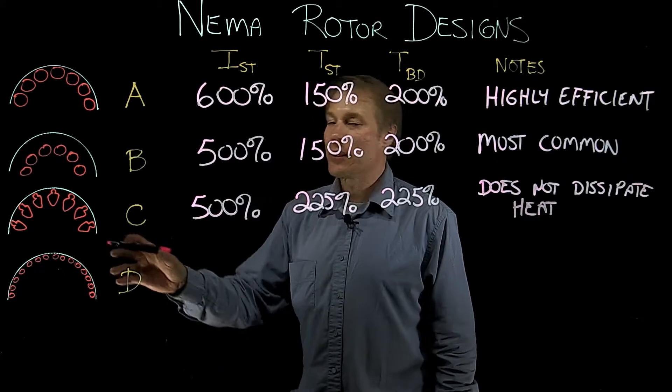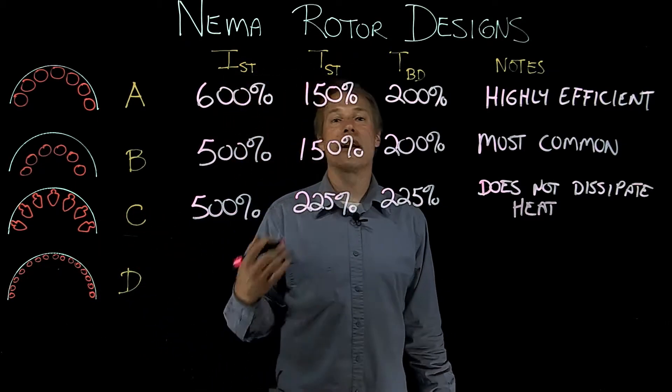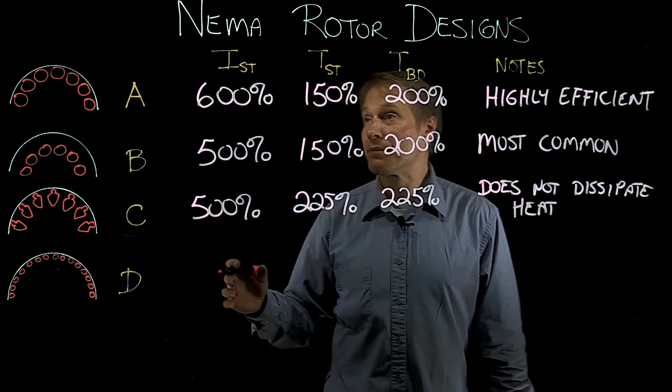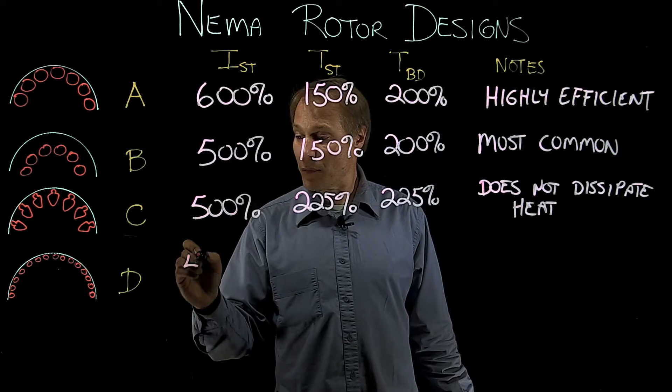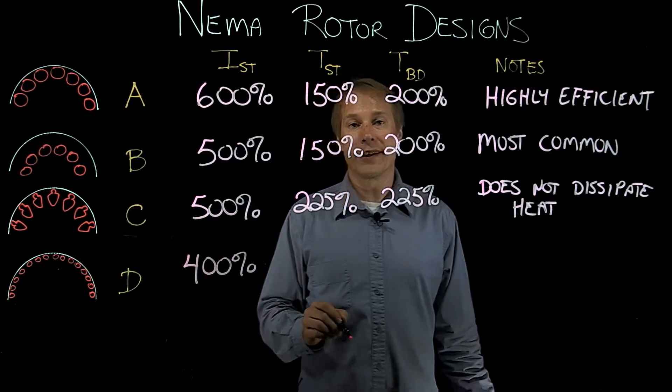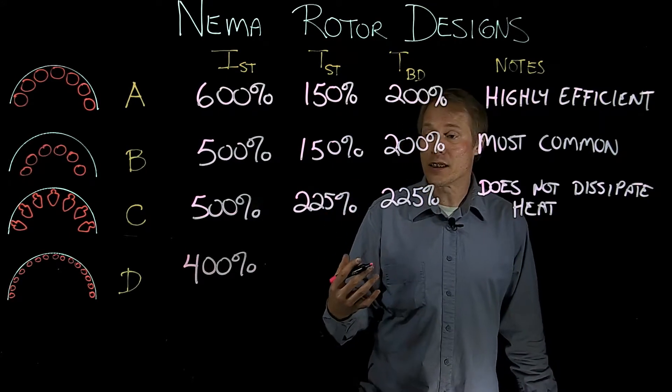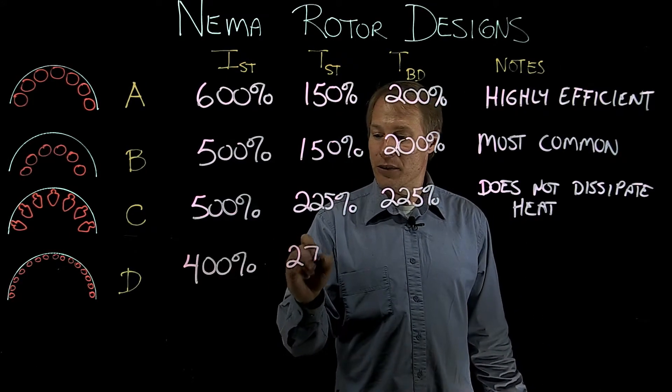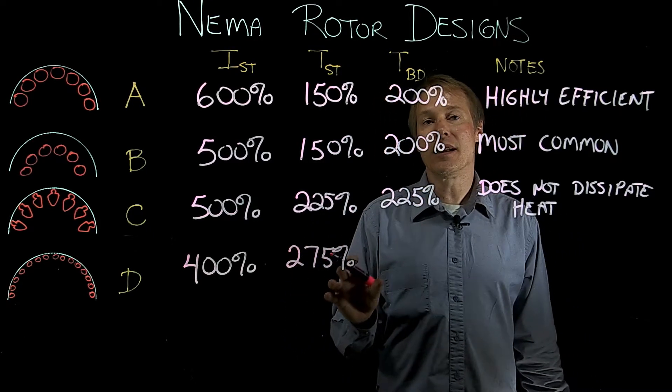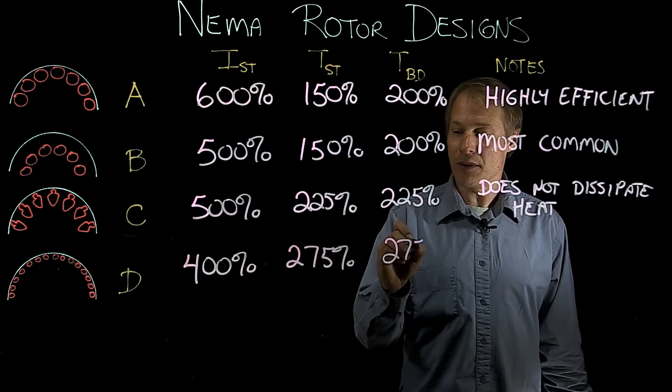And then finally, we've got the NEMA-D design. As you can see, the rotor bars are much smaller, which gives us higher resistance. So that'll make the starting current go down even more. So now we have, let's say, 400% of FLA. But the starting torque will be higher because now it's all resistive. And that'll be around 275%. And the breakdown torque for a NEMA-D is the same as the starting torque. So we're looking at 275% again.